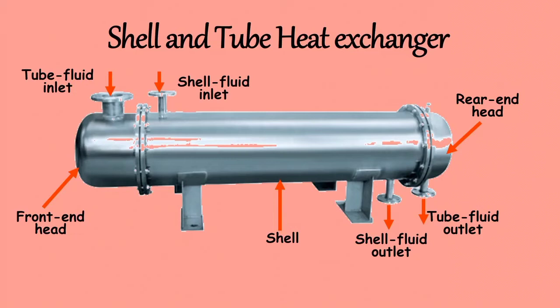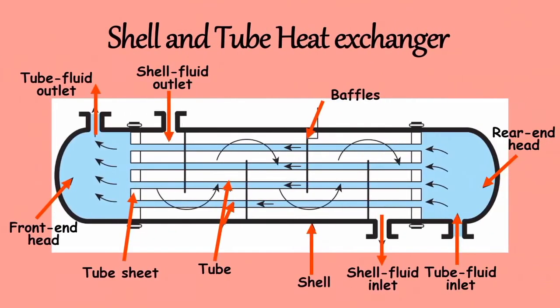Similarly, the major criteria for selection of the rear end head are: the allowance for thermal stresses, a provision to remove the tube bundle for cleaning the shell side, prevention of mixing of tube and shell fluids, and sealing any leakage path for the shell fluid to ambient.